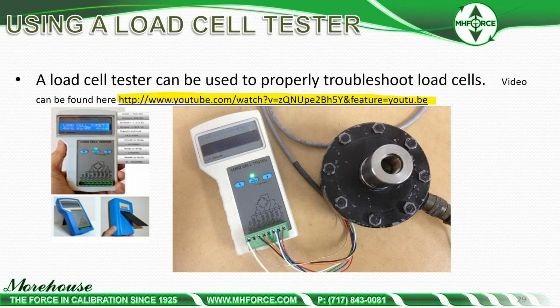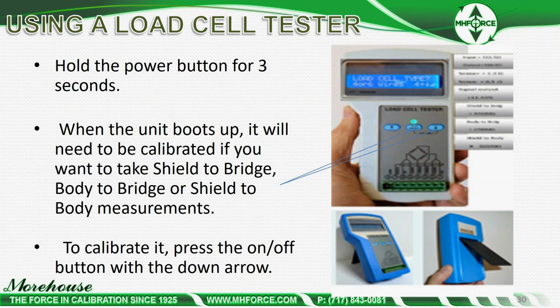So here's how the load cell tester works. You hold the power button for 3 seconds. The unit will boot up. It will need to be calibrated. You can take shield to bridge, body to bridge, or shield to body measurements. Typically, you're not going to do that. You're going to be more concerned with, hey, what's my signal? What's my sense? What's my input and output? And what's that zero balance? But to calibrate it, you can press the on and off button with the down arrow.